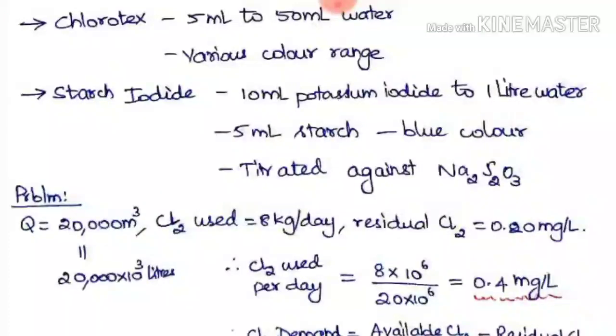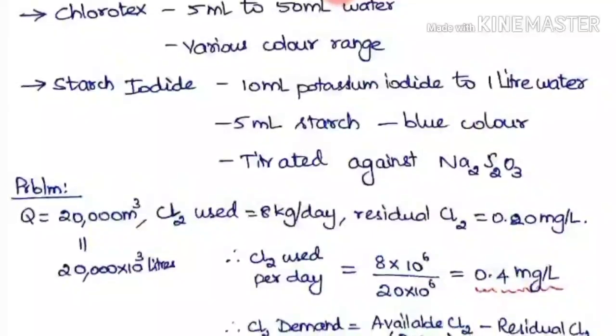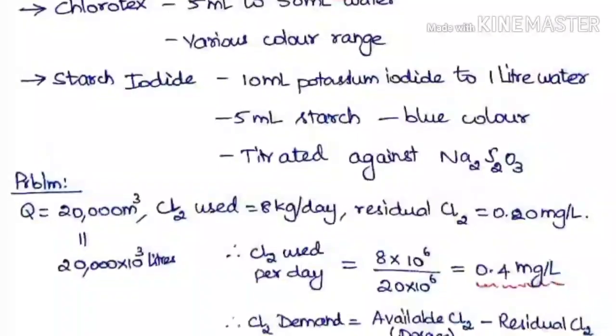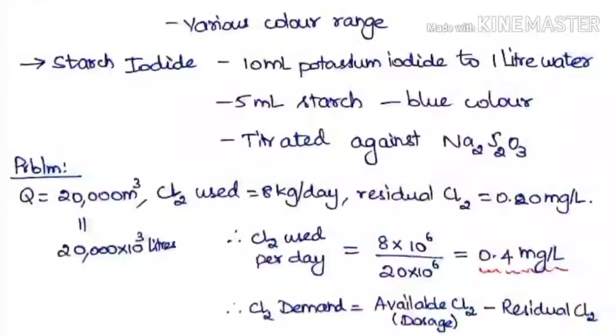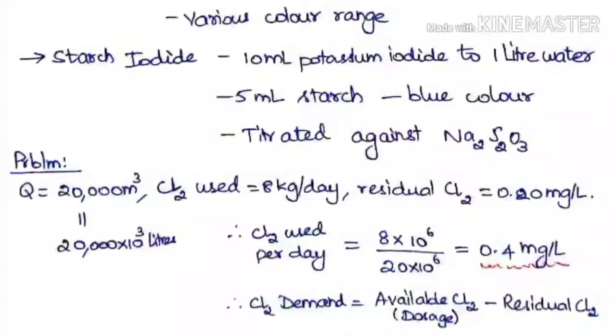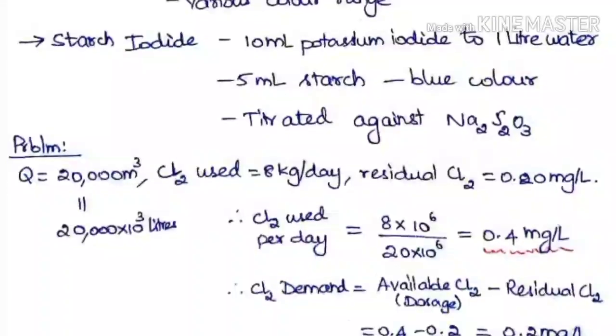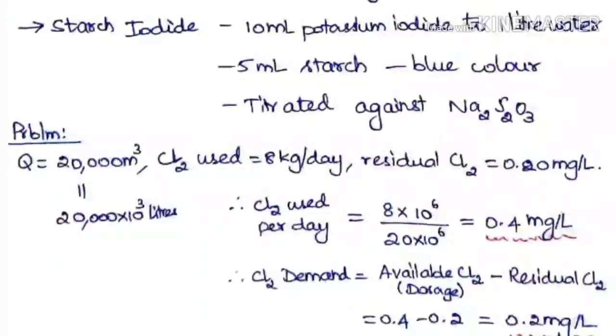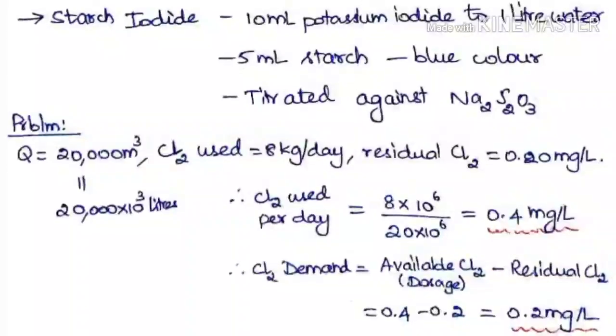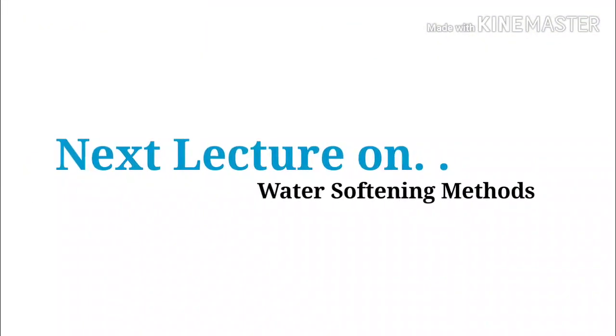The calculation gives a chlorine dosage of 0.4 mg/L. The chlorine dosage equals the chlorine demand plus the residual chlorine. Therefore, the chlorine demand equals chlorine dosage minus residual chlorine: 0.4 minus 0.2 equals 0.2 mg/L. So the chlorine demand is 0.2 mg/L.